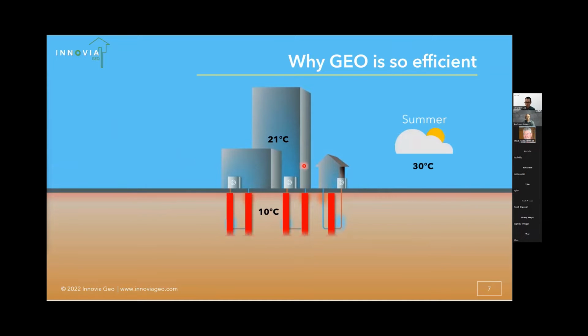Similarly in the summertime, if we're cooling the building with the ground at 10 degrees Celsius, it's extremely efficient and easier to do, and will take a lot less energy than if we're trying to move that heat when it's, just like today, over 30 degrees outside and pretty hot. So that's where that efficiency comes from.